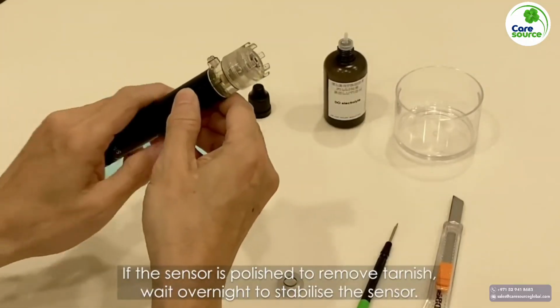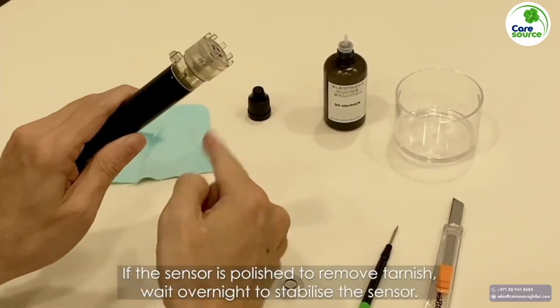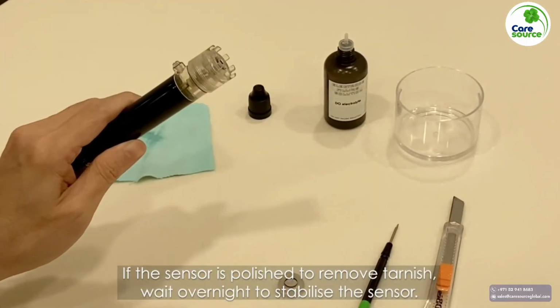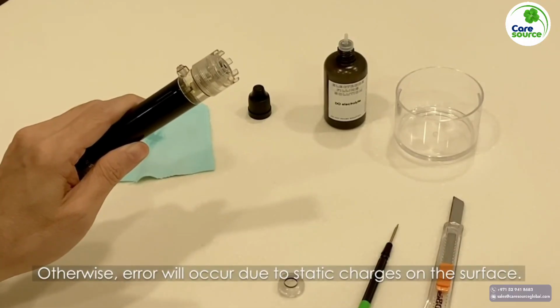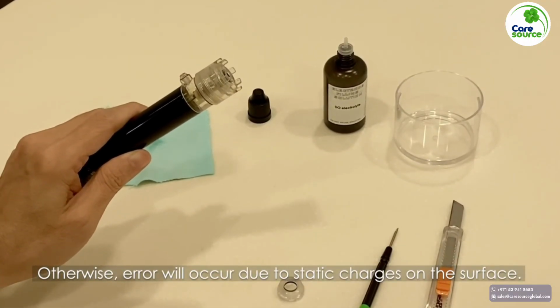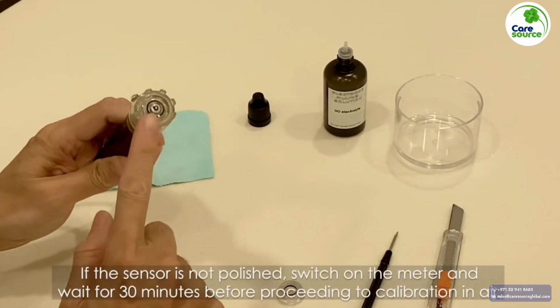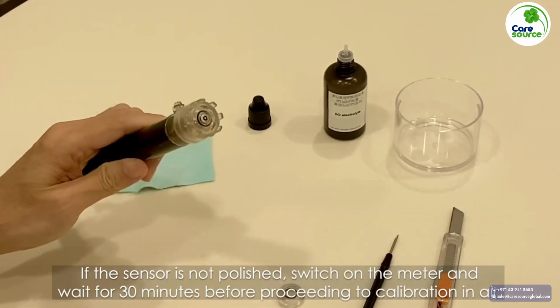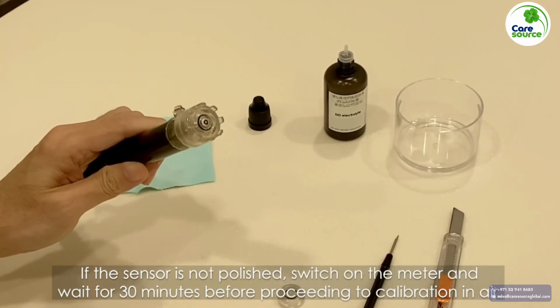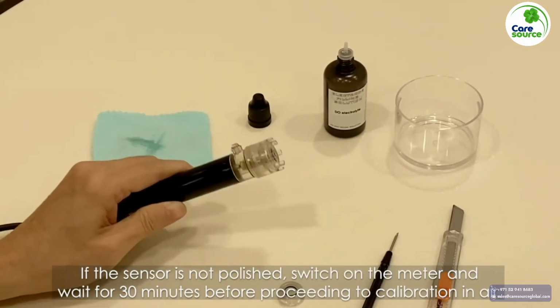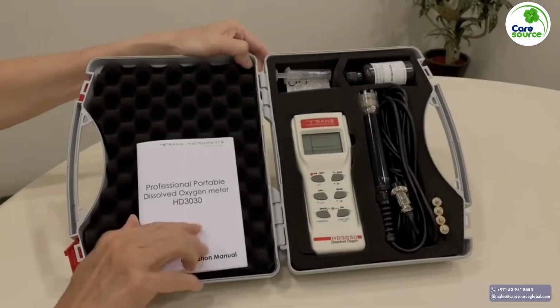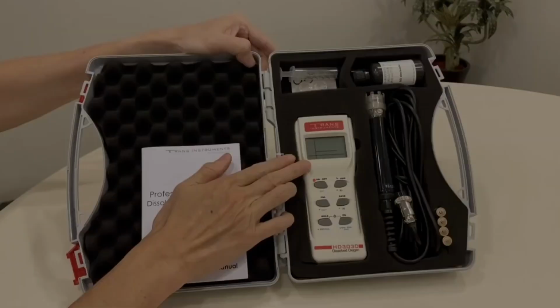If the sensor is polished to remove tarnish, wait overnight to stabilize the sensor. Otherwise, errors will occur due to static charges on the surface. If the sensor is not polished, switch on the meter and wait for 30 minutes before proceeding to calibration in air. That is all for the brief introduction to the HD3030.